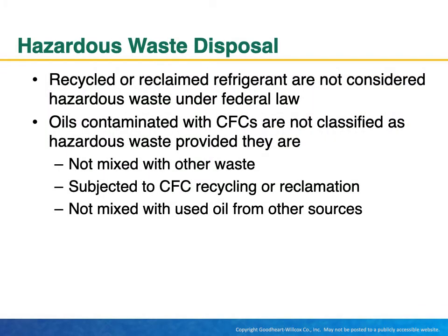Hazardous waste disposal. Recycled or reclaimed refrigerant are not considered hazardous waste under federal law. Oils contaminated with CFCs are not classified as hazardous waste, provided they are not mixed with other waste subject to CFC recycling or reclamation, not mixed with used oils from other sources.